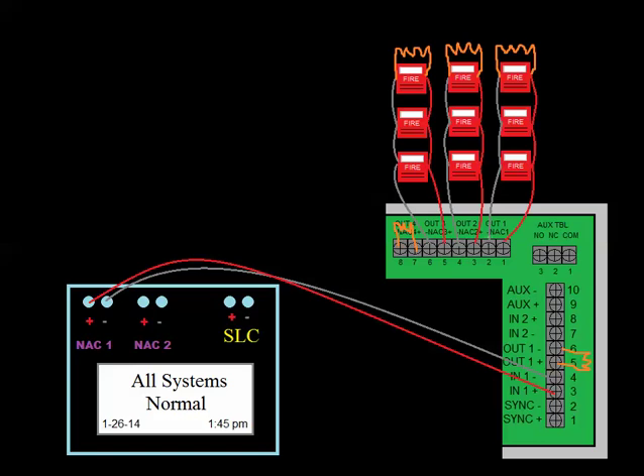So quickly, this is a drawing of an addressable fire alarm panel. It's using its NAC to trip the FCPS. So in a normal state, the red wire here, this positive terminal, if you metered these two terminals, they would actually have negative voltage on them.